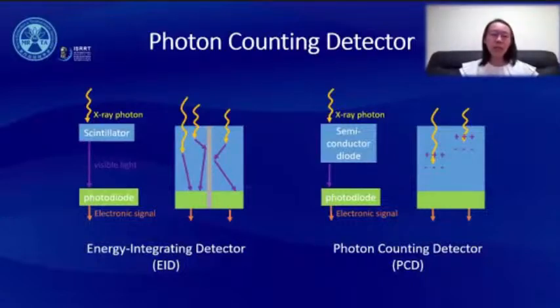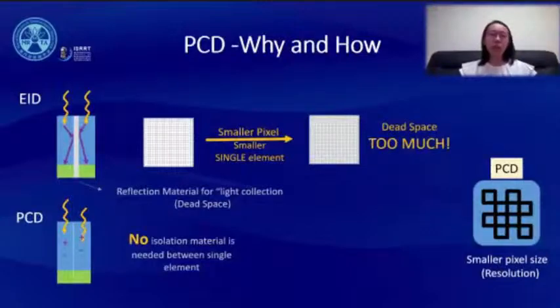And on the right hand side is the new PCD, and we can see that the incident X-ray is measured directly by generating a cloud of positive and negative charges. The electronic circuits separate and pull them away quickly and register them as an electronic signal. And this is what we call one-step direct conversion. The one-step conversion and two-step conversion make a difference between these detectors. Let's have a look at that.